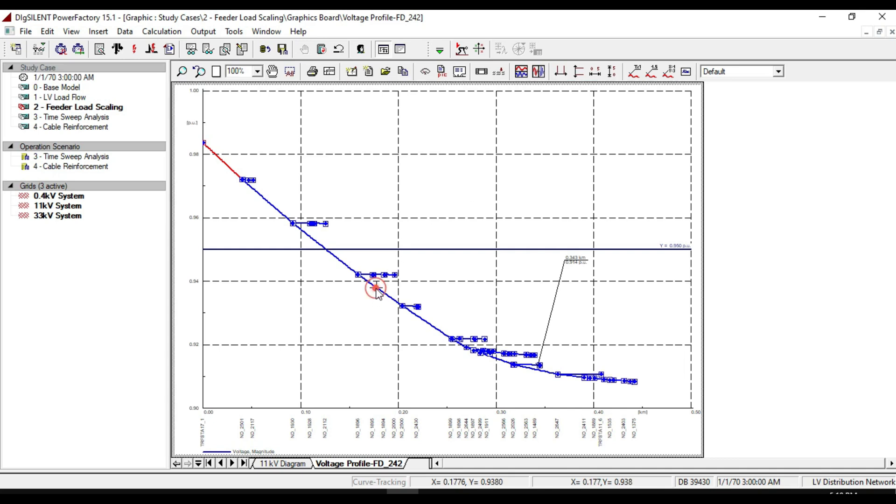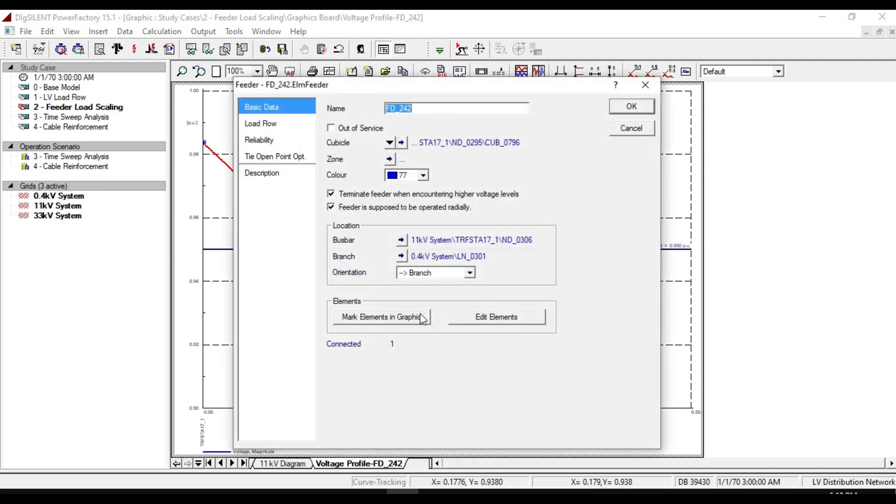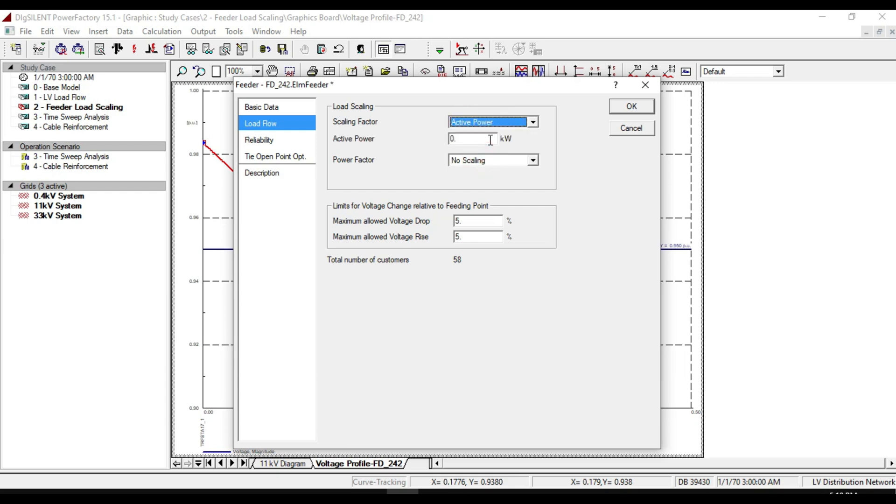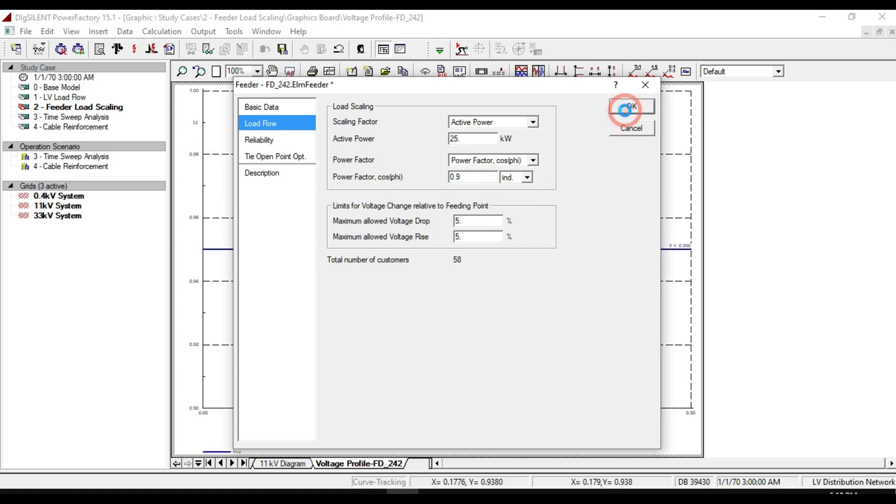Right-click on the characteristic and select edit feeder. From the load flow tab, select active power for scaling factor and suppose 25 kilowatts for active power. Select power factor and set it to 0.9, then click OK.